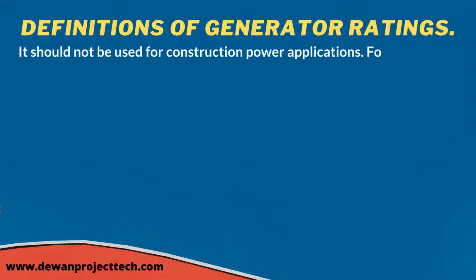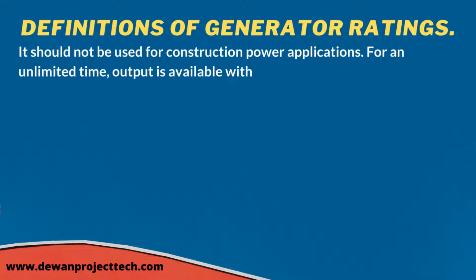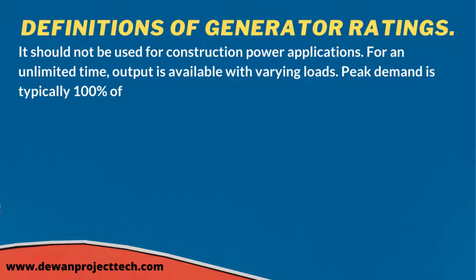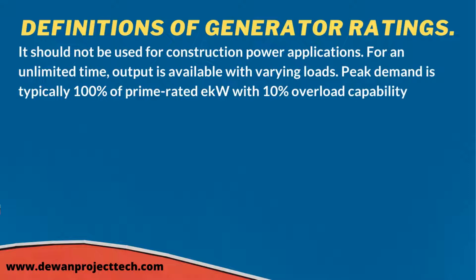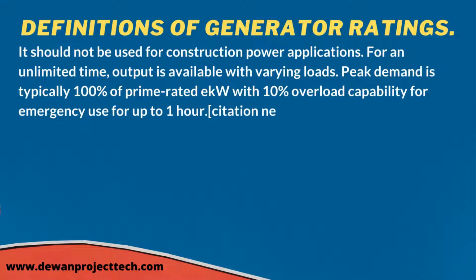Definitions of generator ratings: it should not be used for construction power applications. For an unlimited time, output is available with varying loads. Peak demand is typically 100% of prime rated, with 10% overload capability for emergency use for up to 1 hour.